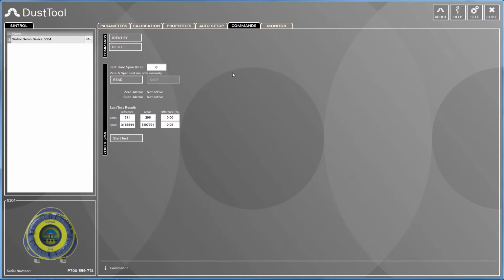The lower part of the Commands tab is about the zero and span check. The first field right on top defines the zero and span check interval. This is set as a default to be 0, meaning no automatic zero and span check takes place. This field equals the parameter 9 of your local button interface and local display.